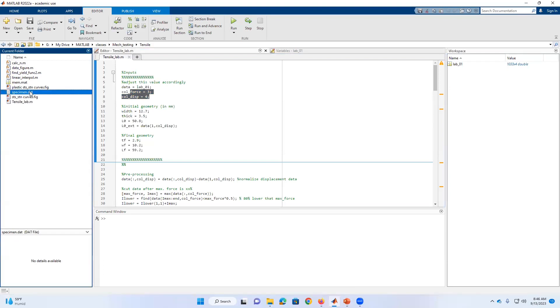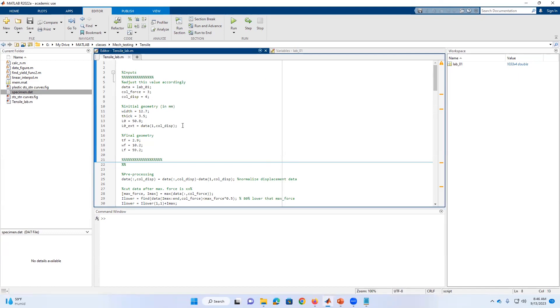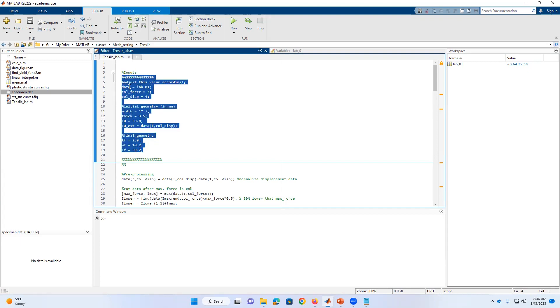The extra inputs are experimental data that you need to measure manually using calipers or any other measurement system. In this case, we are running tensile tests for flat specimens, so we have the width and thickness of the specimen, and the initial gauge length marked between two points. We also have the final thickness, final width, and final length to calculate the elongation and reduction of area. Those are the basic inputs that we need to place.